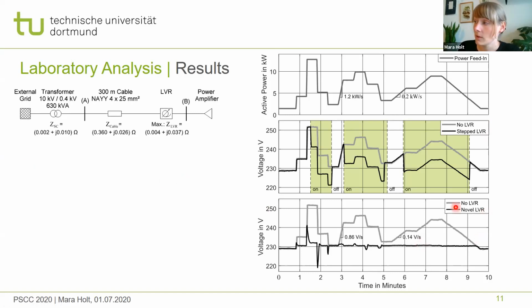The novel line voltage regulator adjusts the voltage at busbar B in a continuous way by tracking a set point of 230 volt. Due to the slow control, rapid voltage variations initially result in control deviations. You can see here. However, gradients of 0.14 volts per second can be completely compensated. With a voltage rise above 250 volts, the control range of the new line voltage regulator is exceeded, but still the voltage is reduced with a maximum range of 20 volts. As the voltage follows a set point, there are less voltage fluctuations and the dynamic voltage characteristic is improved.